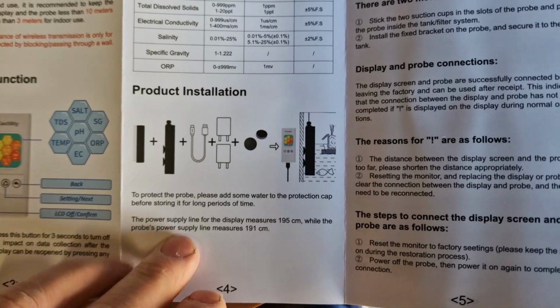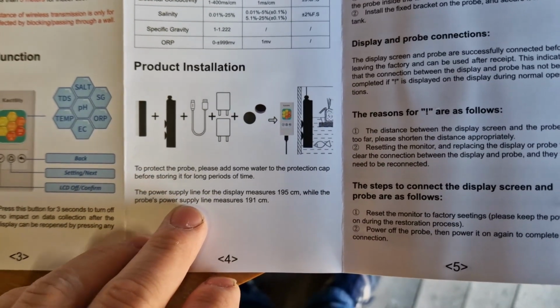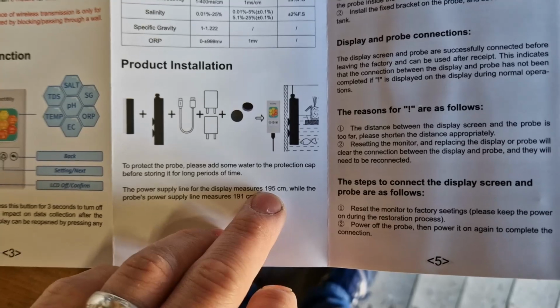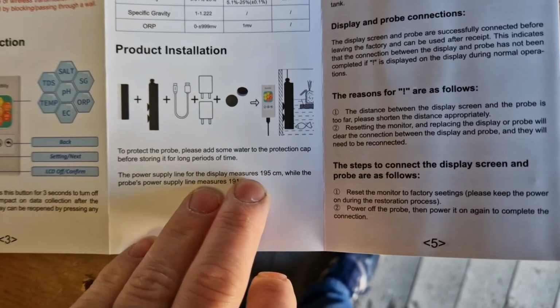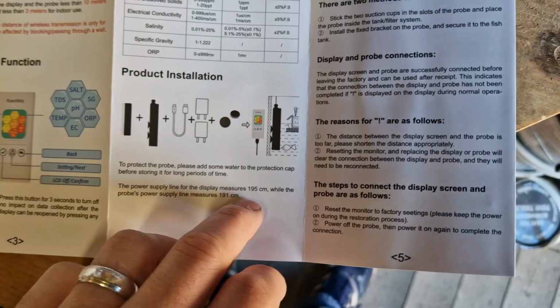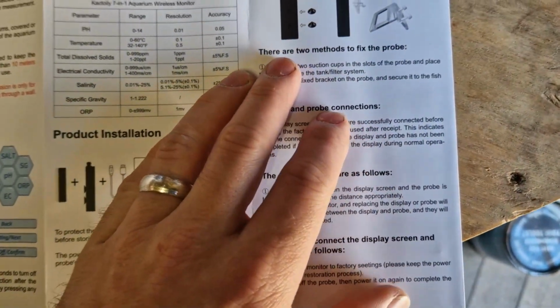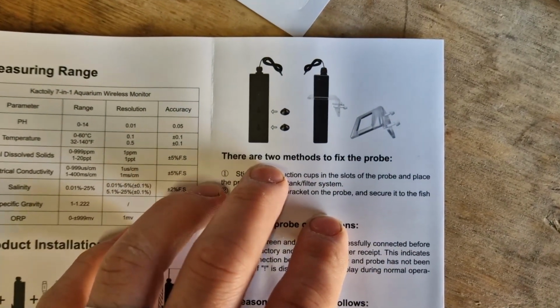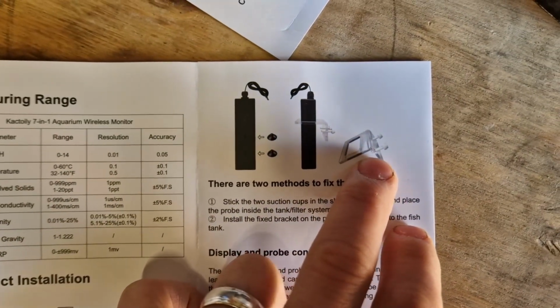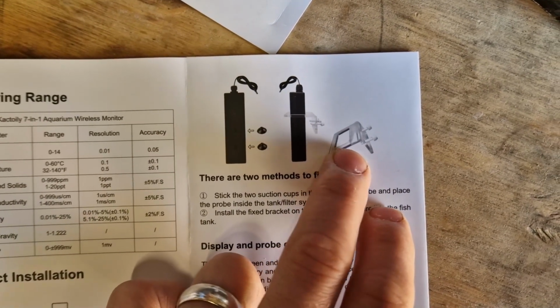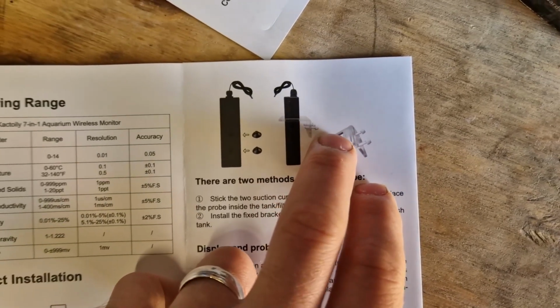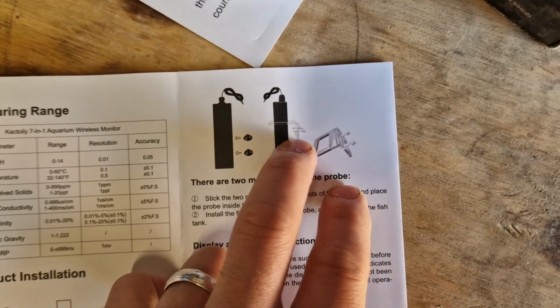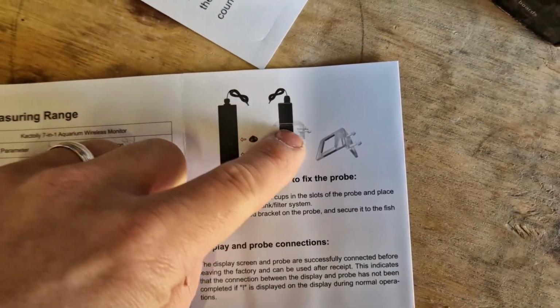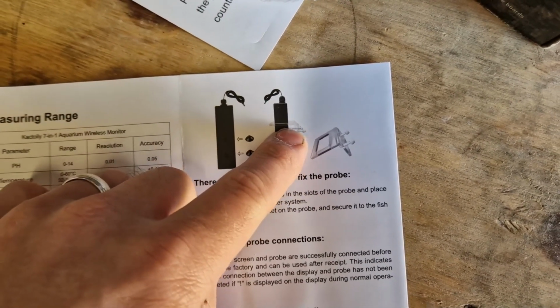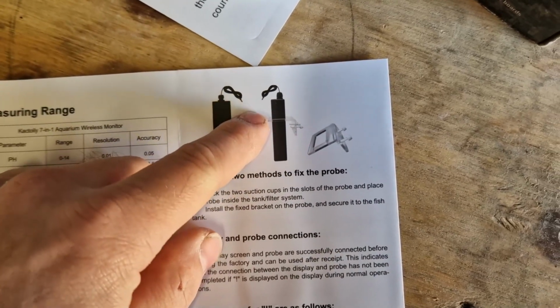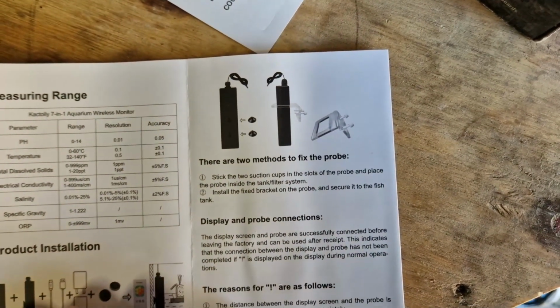So to protect the probe, the wires are 195 centimeters and 191 centimeters, so they're pretty lengthy cables, to be fair. Fixing methods for the probe. So as you can see, this is the way you fix it if you're going to use the bracket. These two screws tighten up to secure the bracket up against the filter. So I think I'm probably going to be using the bracket inside the drum filter, and just sit the probe inside it, just like that.